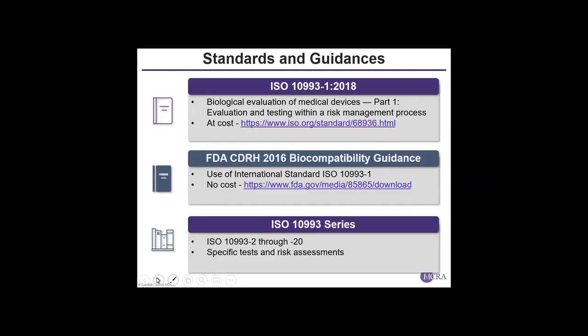So if it seems like there's a lot to remember there, that's true. But the good news is this information is all documented in standards and guidances that you can have access to. So the overarching standard for biocompatibility is ISO 10993 Part 1, published and released in 2018. And then we also have a guidance document from FDA released in 2016. This guidance document explains FDA's interpretation of an earlier version of that standard. And finally, we have a whole series of other standards in the ISO 10993 series. These standards cover the specific tests and risk assessments used for each of those biocompatibility endpoints we discussed earlier.